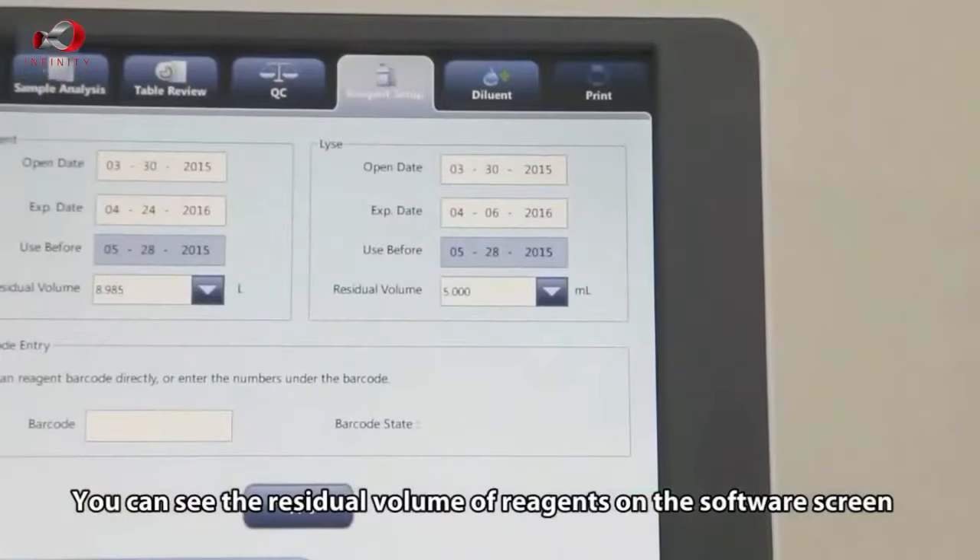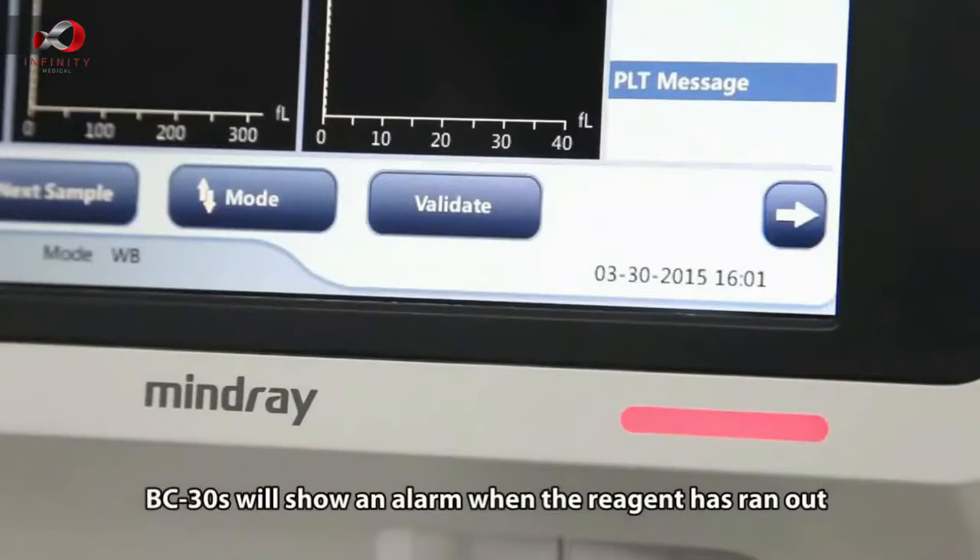You can see the residual volume of reagents on the software screen. The BC-30s will show an alarm when the reagent has run out.